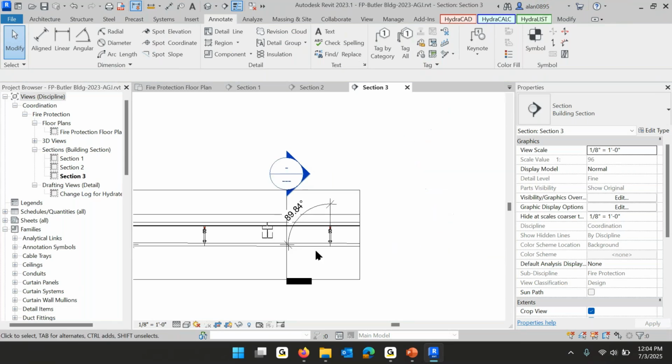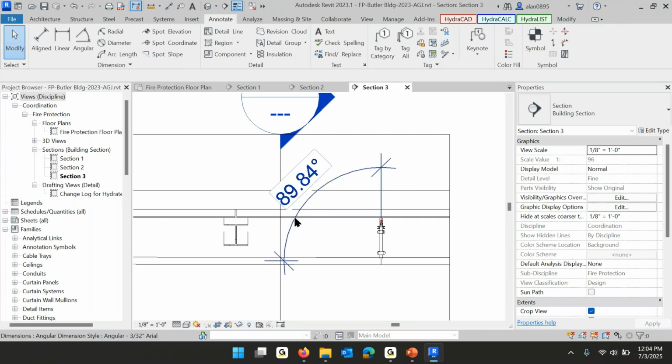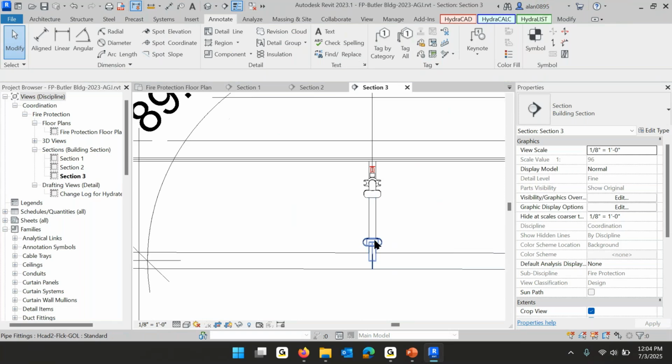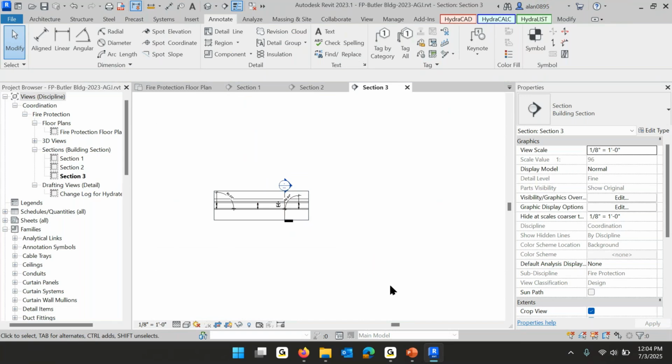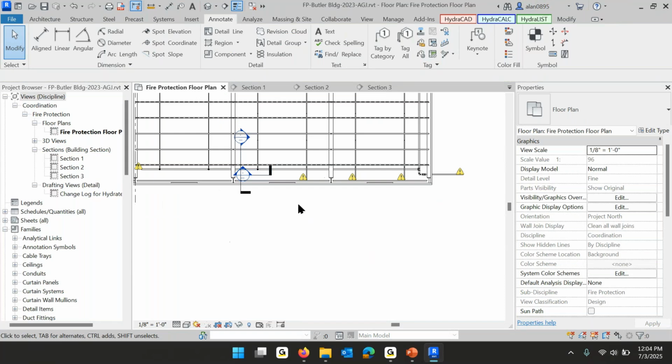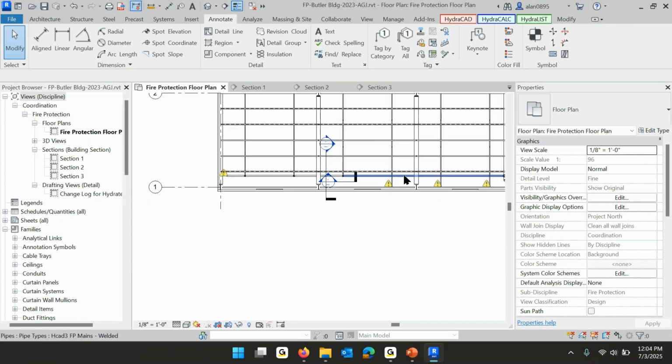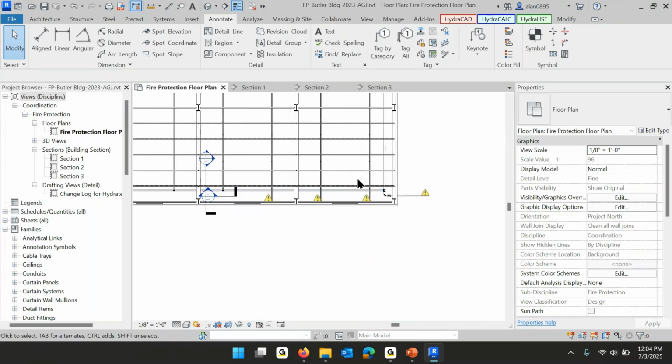If I had seen or remembered this, I might have said, yeah, most of the time that's going to be close enough, because you can get 0.2 degrees out of that coupling easy. Mm-hmm. Yeah. But at least I can say, yeah, it was not for naught. We did precisely the exact right thing on that. Yep. So I've done 3. I'm going to call that one Dave's one close enough, and I'm just going to go do the other 3 here.